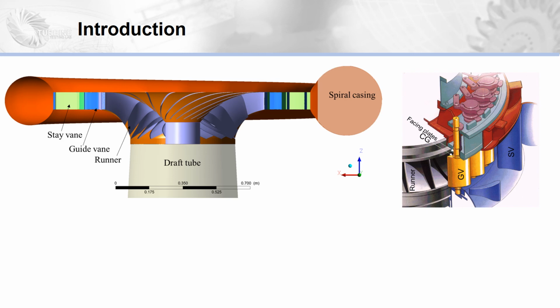As we all know, guide vanes are an important part of the Francis turbine that contributes to the conversion of total available hydraulic energy partly into acceleration energy. Flow while entering the guide vane experiences acceleration. These high velocities of the fluid leaving the guide vane enter the runner at a designed angle. This imparts rotational kinetic energy to the runner blades, and the flow leaves the runner domain through the draft tube. This is how a typical Francis turbine works.